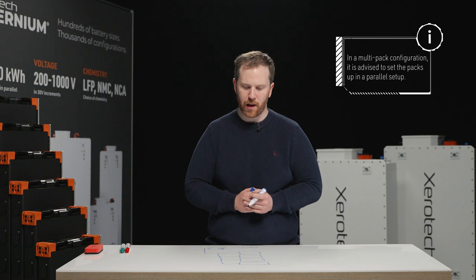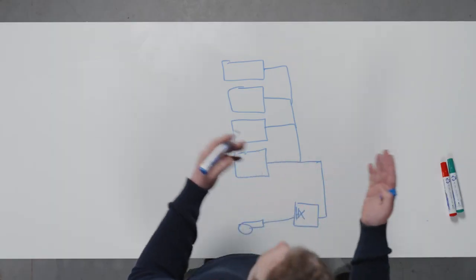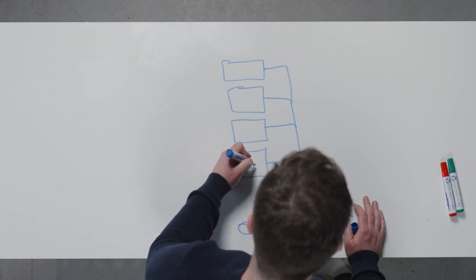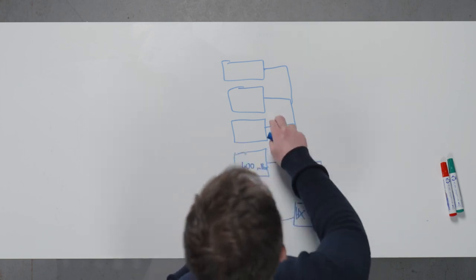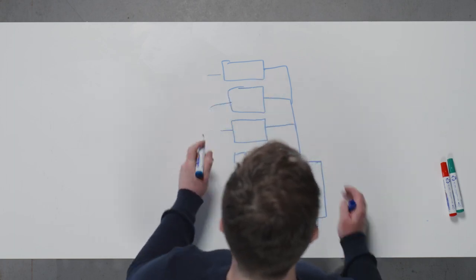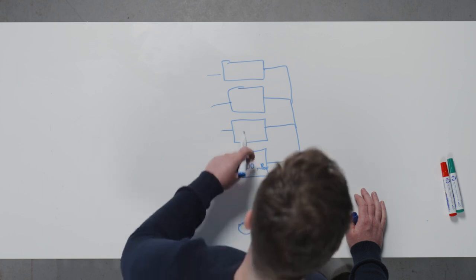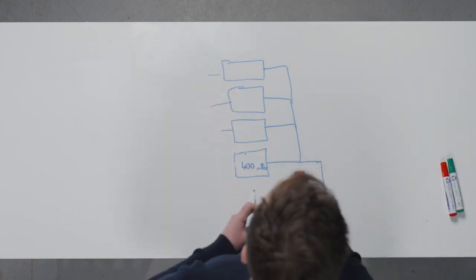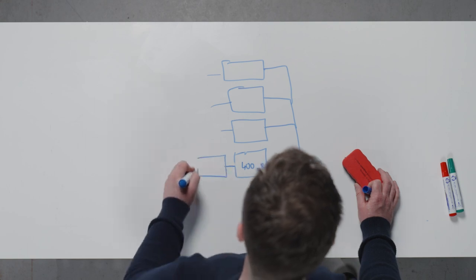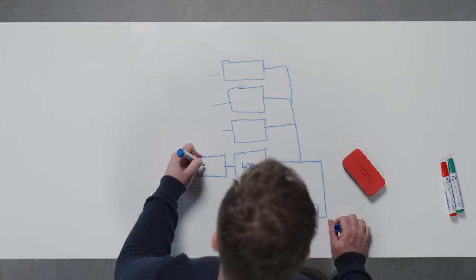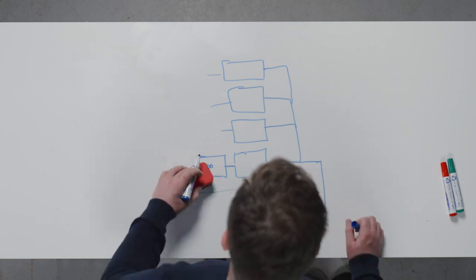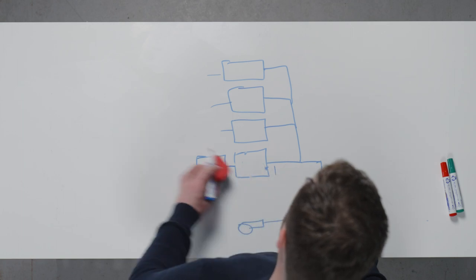It's better to put the packs in parallel because that means they will have the lowest pressure drop because there's more parallel paths. So every pack you put in parallel will reduce the pressure drop. So let's say, for example, the pressure drop of one pack at a particular flow rate is 400 millibar. By putting 4 in parallel, you decrease the pressure drop of this circuit to 1/4 of that. So it's decreasing every time. So it's better to put things in parallel. If you put 2 packs in series, the pressure drop will not be halved, it will be doubled. It will now be 800 millibar at a system level across this circuit. Sometimes that can be acceptable, and we'll talk about that in a moment.